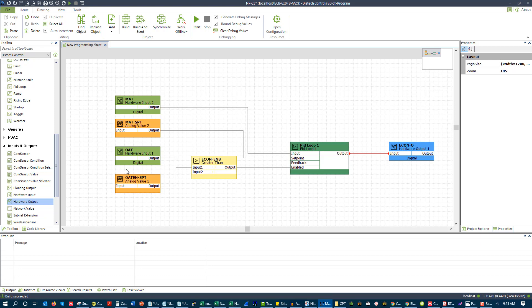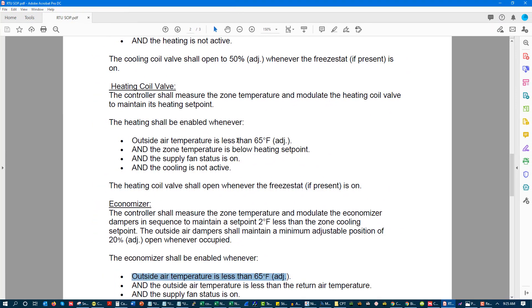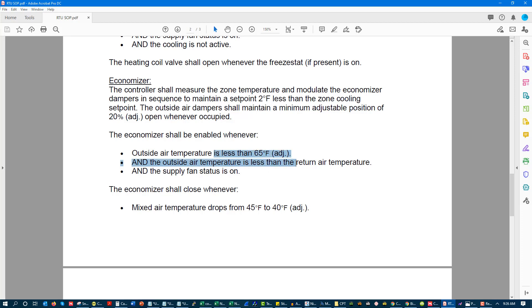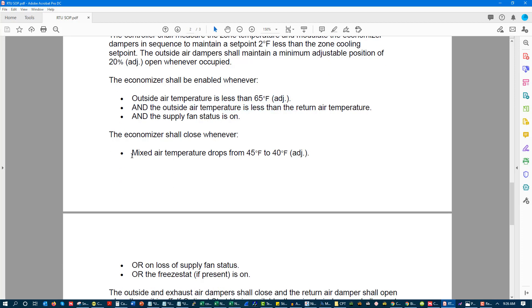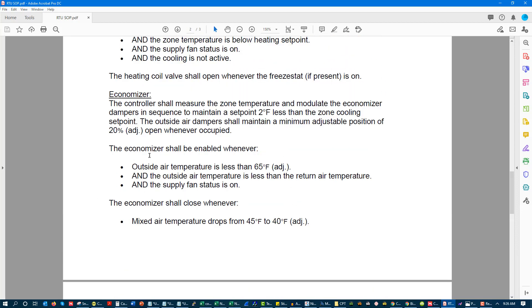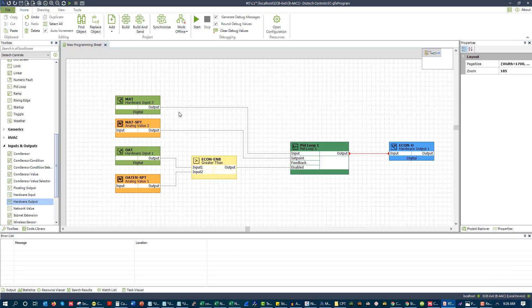We have our comparative pattern. So if I read anything where it says 'when X' — let's look at this sequence over here — when outside air is less than 65, that's a comparative pattern. Outside air temp is less than 65, comparative pattern. Mixed air temp drops from 45 to 40, hysteresis pattern. So we're starting to see all these different patterns. And I see 'controller shall measure zone temp and modulate heating valve to maintain heating set point' — that tells me PID loop pattern. As I start to read these sequences and I know my design patterns, I'm able to program.